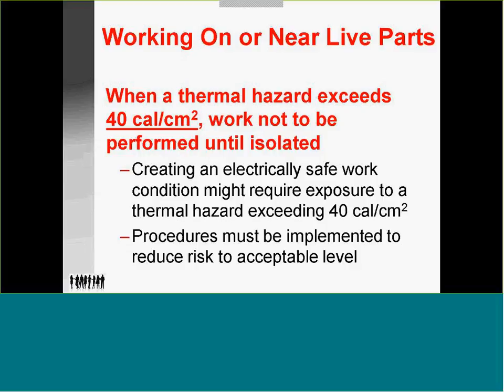When it exceeds 40 calories per square centimeter, work is not to be performed until isolated, period. This is a serious issue. Now, there are some suits coming into the United States that are 150 calorie rated. The problem is when they're being tested, they're not holding up. Now, they prove it all the time, so these tests are ongoing to make sure they can hold out whatever they're saying they can hold out. The unfortunate part is if you take a 140 calorie per square centimeter blast in a 150 calorie suit, it's possible to roast you inside the suit without you ever being severely burned by the blast itself. It just heats up. It's like a potato in tin foil and putting it in the oven. So this is very misconstrued at times.